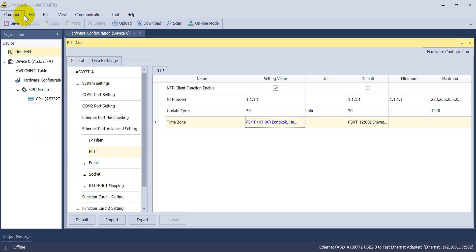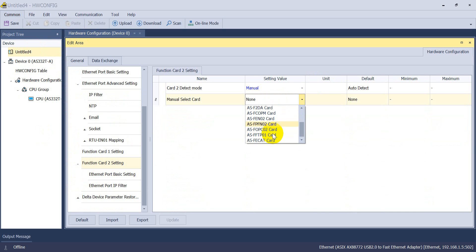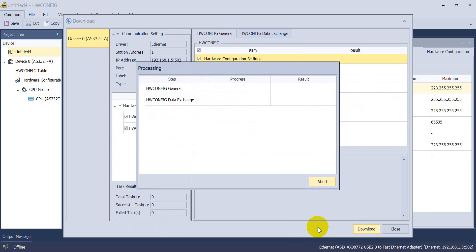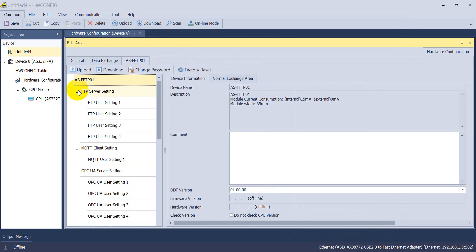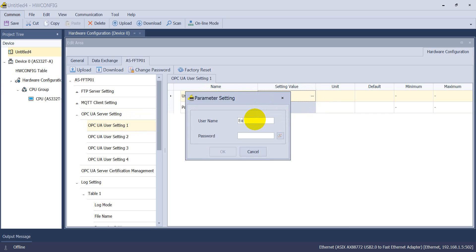Now switching back to hardware config. In the Function Card 2 settings, change to Manual, then select the FTP function card with IP address ending in .1.6, click Download, then Close. Select the FTP function card and go to the OPC UA server setting. This option is for anonymous login. Here we create the username and password — the OPC UA function card supports up to four sets of username and password. We select username 'i4' and password 'i4-1234'.